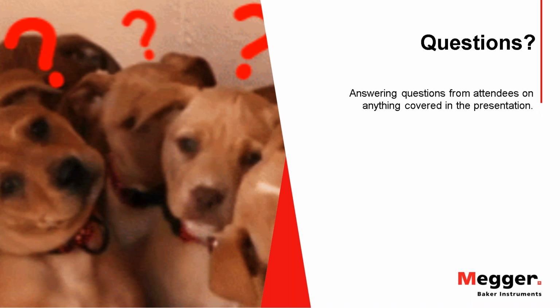Although, again, I did mention that 80% of the insulation failures begin as turn-to-turn faults. So if I had to give a little more weight, I would put it in the surge category. But high pot testing evaluates the entire ground wall insulation. So again, it's one of these cases where neither one replaces the other. They each tell us a little bit of something different, but surge test is probably the primary driver towards most electrical insulation failure.